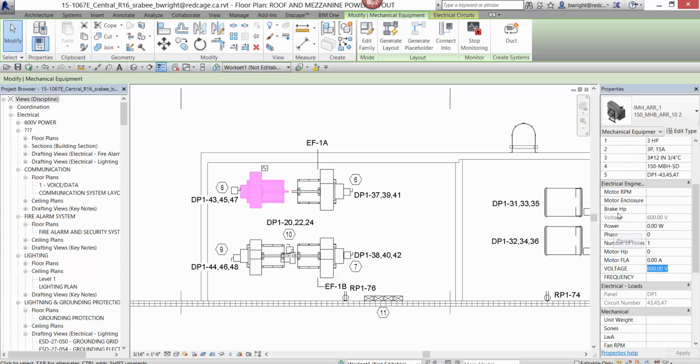Every parameter that you create has this ID number in the back end of it, this GUID number or whatever, right? And if you create a voltage parameter and you download a family and it says voltage parameter, they may not schedule in the same column because they were created using 2 different ID numbers in the back end that Revit understands.